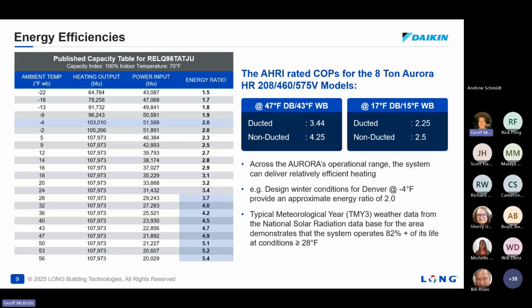If you go to 28 degrees, which I'm going to highlight here, it says 3.7. The system in Denver is going to operate at 82% plus of its life at 28 degrees or higher. And essentially that 3.7 means it's a 370% efficient unit. So there are some variables in this. This isn't perfect science, but this is the gist, just to show how efficient these electric heat pumps really are, and how that can cut into the fact that gas has been artificially cheap for a long time.